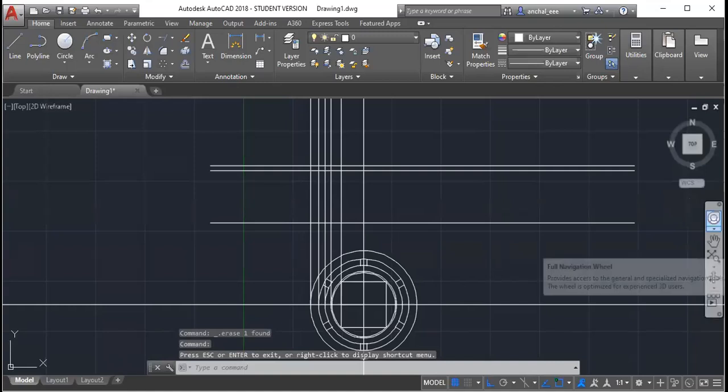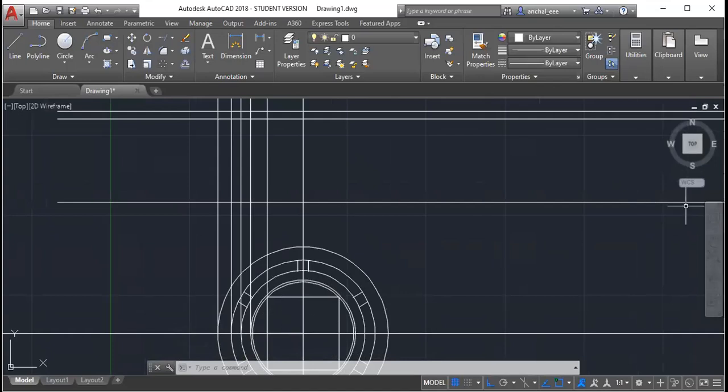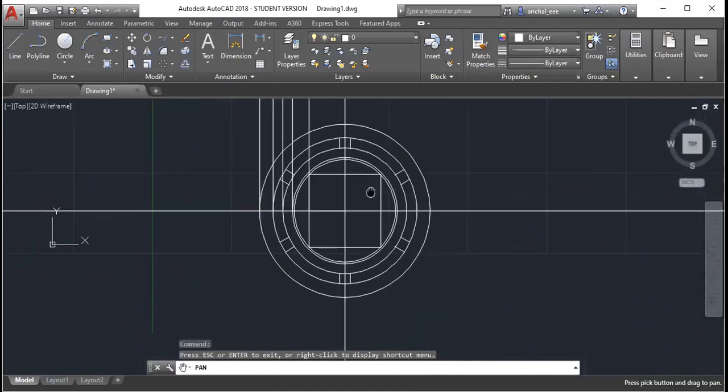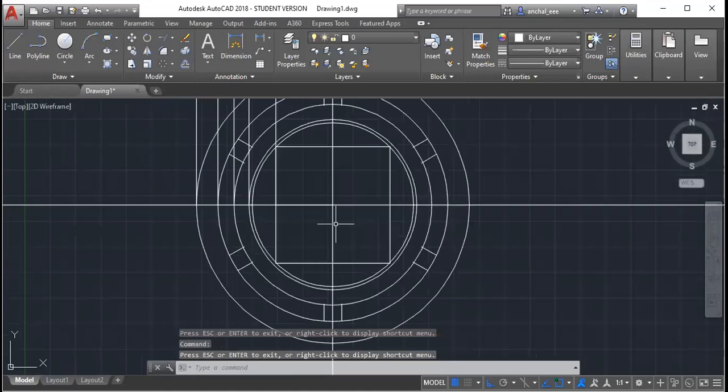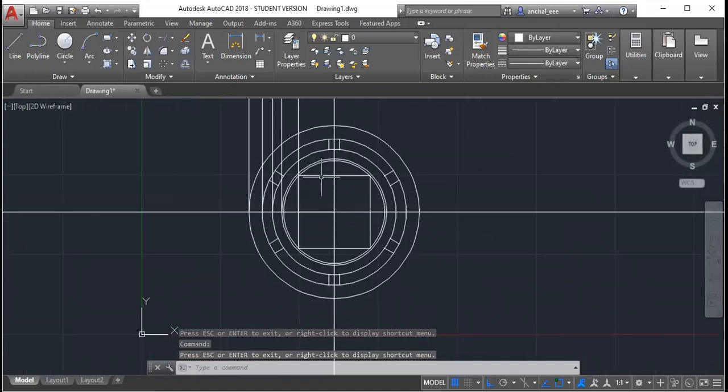See, the circumcircle dia is 80 mm, right? So for a single step core, what we do, we multiply 80 mm, that is the circumcircle dia, with 0.71. When you multiply 80 with 0.71, you will get 56.8. Fine. I will draw it again for you. Wait. Otherwise, you will not understand.